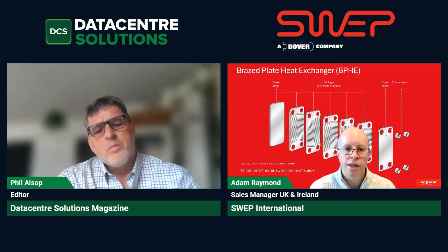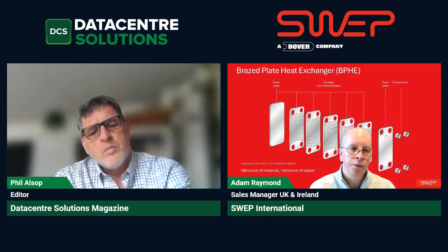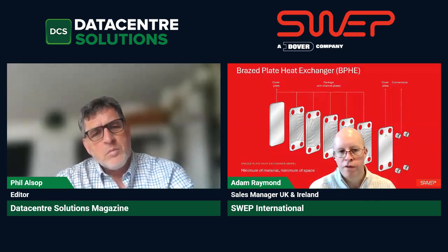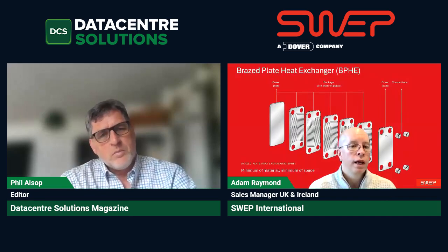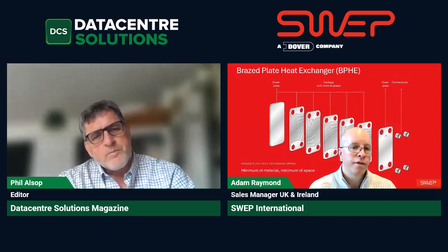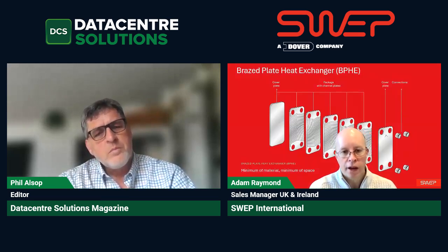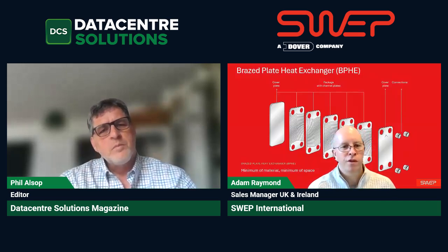So using the liquid itself is probably the most easy and obvious choice. But then we also have the ability, if the data center is cooled with what we call mechanical cooling or refrigerant-based chiller systems, to intercept the refrigerant gas. So the hot refrigerant gas can be captured, if you will, and then that can also be used for water heating. In the case of the eco data center, it's quite a novel approach, actually, what they've done.